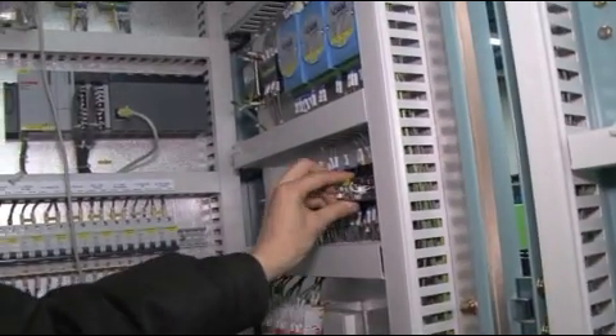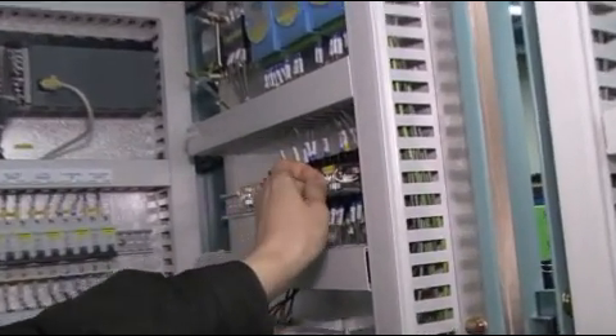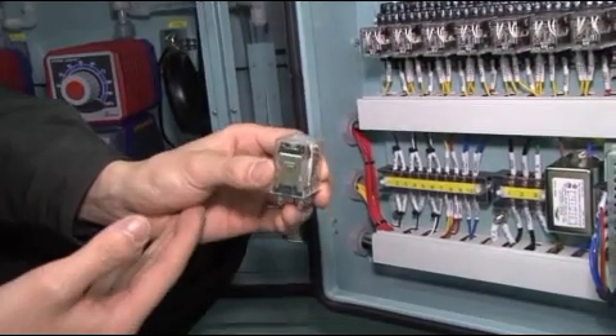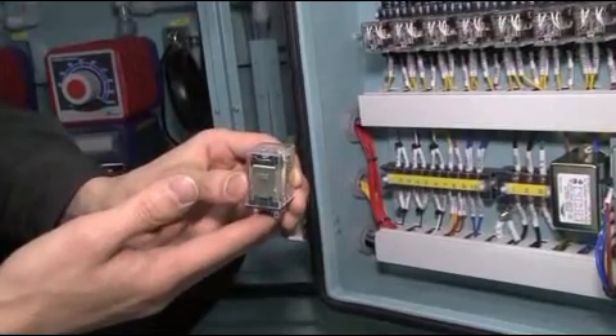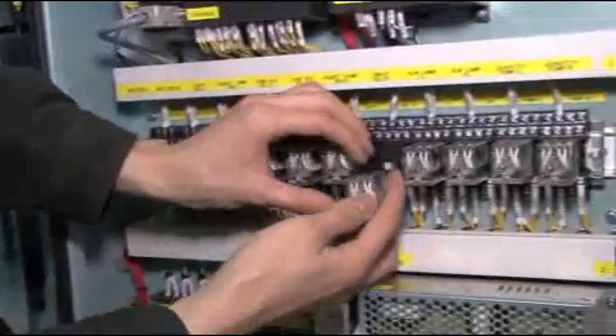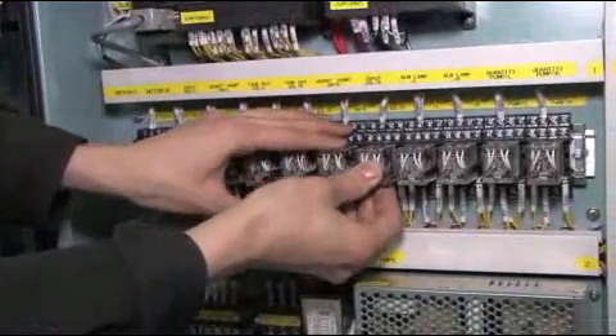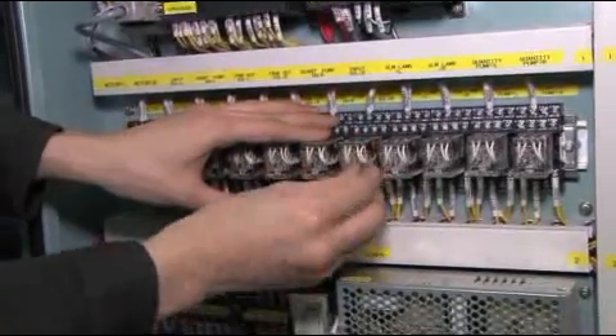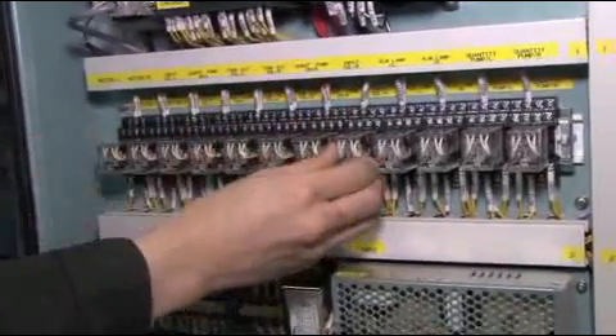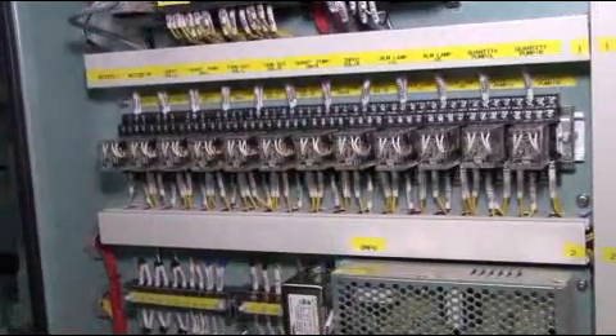Step 3. Install a new relay in the relay socket after checking voltages. LED lamp color, red AC 220V, blue DC 24V. Step 4. Check the operation, LED lamp light and operation state.